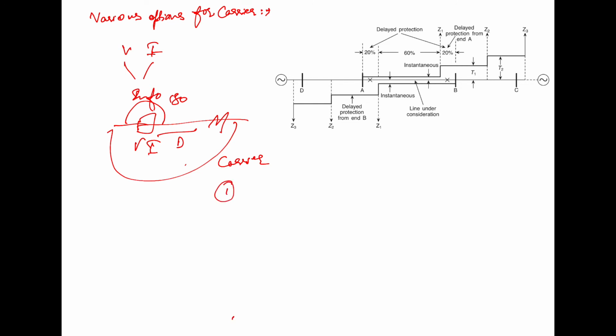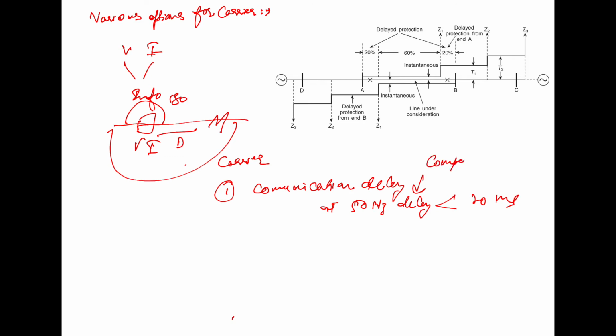The delay involved in communication should be small. It should be less compared to the time period of the system frequency. At 50 Hertz, the delay should be much less than 20 milliseconds. Now, since only a small amount of information is to be passed, the carrier channel need not have very high bandwidth for protection purposes.